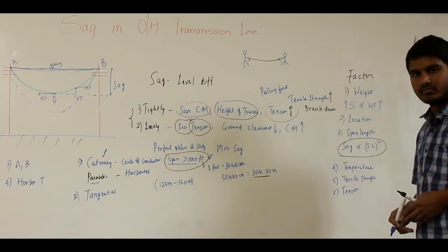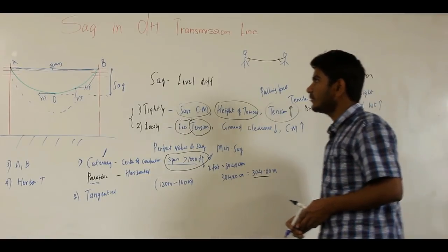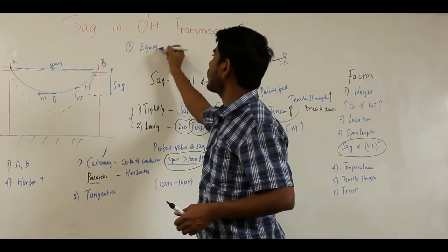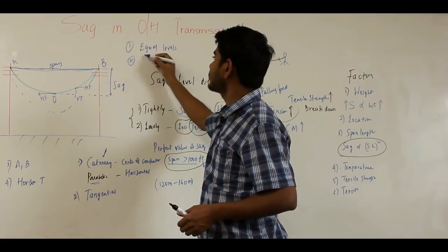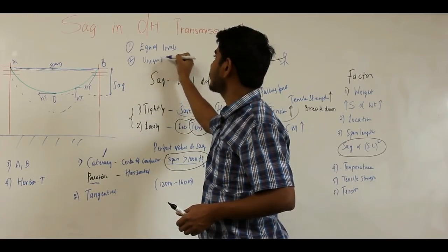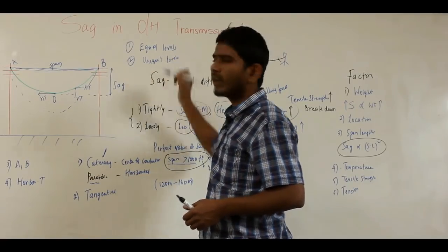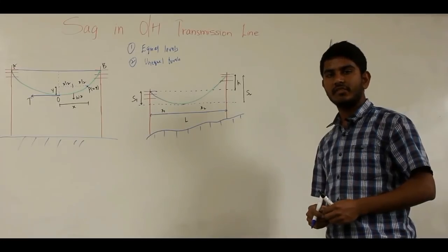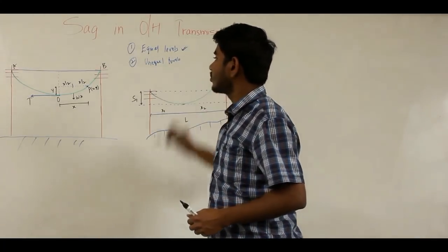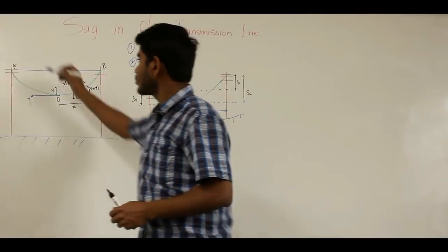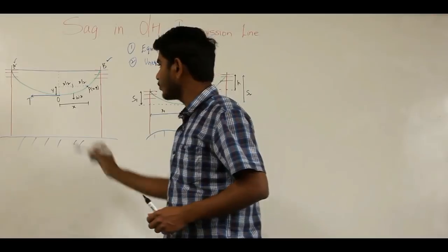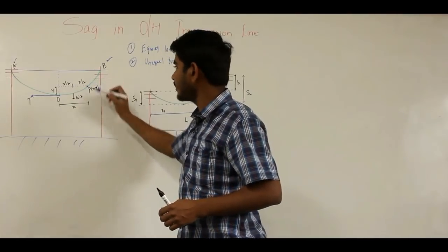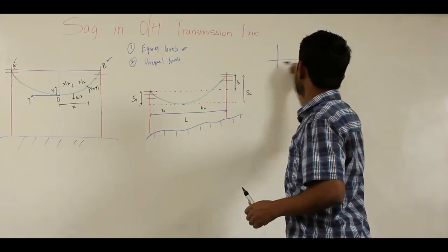Sag calculation can be made under two conditions: support points at equal levels, and support points at unequal levels. For support points at equal levels, consider the two support points A and B, with O as the lowest point on the conductor where tension T acts, and a point P on the conductor with coordinates X and Y, taking O as the origin. X is the horizontal distance and Y is the vertical distance from O to P.